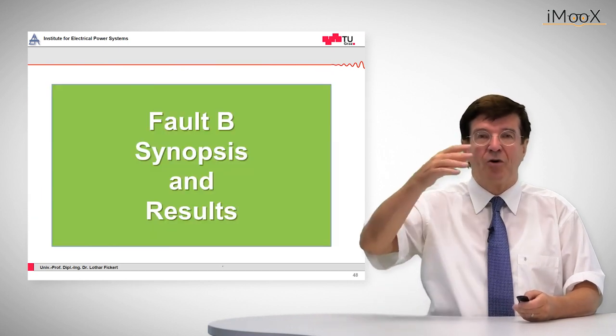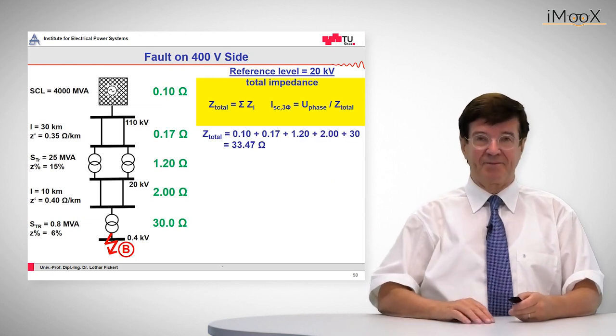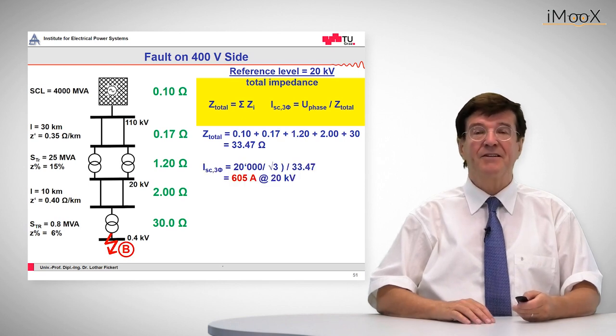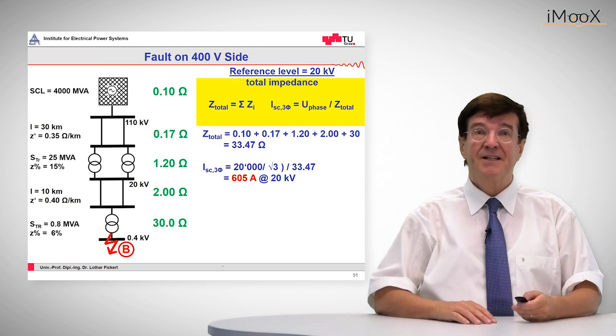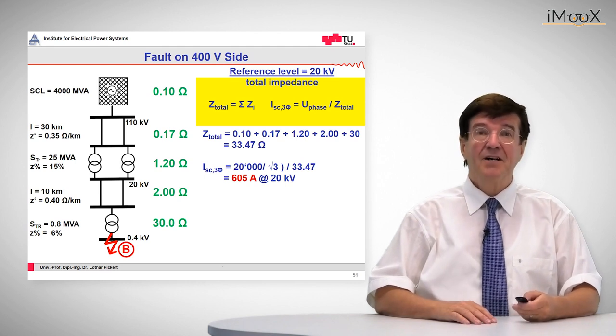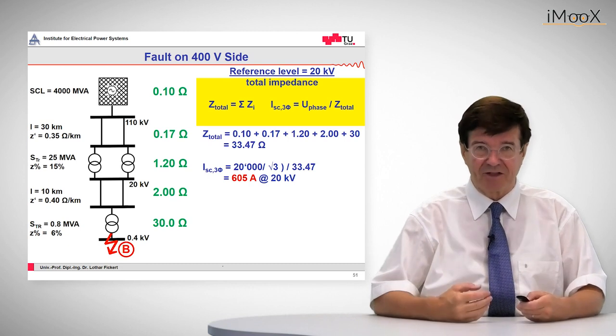Now we add all these impedances up, obtain a total series impedance of 33.47 ohms, and divide the phase voltage by this value. The outcome is 605 amps on the 20 kV voltage side, which is our reference voltage level.